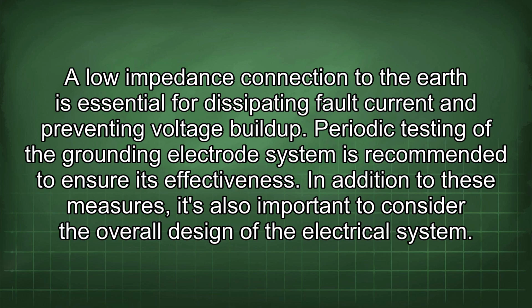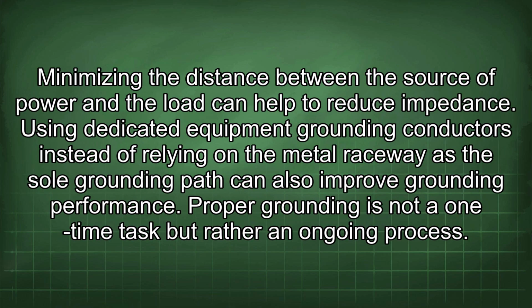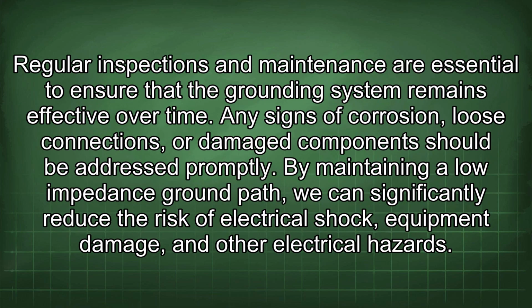In addition to these measures, it's also important to consider the overall design of the electrical system. Minimizing the distance between the source of power and the load can help to reduce impedance. Using dedicated equipment grounding conductors instead of relying on the metal raceway as the sole grounding path can also improve grounding performance. Proper grounding is not a one-time task, but rather an ongoing process. Regular inspections and maintenance are essential to ensure that the grounding system remains effective over time. Any signs of corrosion, loose connections, or damaged components should be addressed promptly. By maintaining a low-impedance ground path, we can significantly reduce the risk of electrical shock, equipment damage, and other electrical hazards.